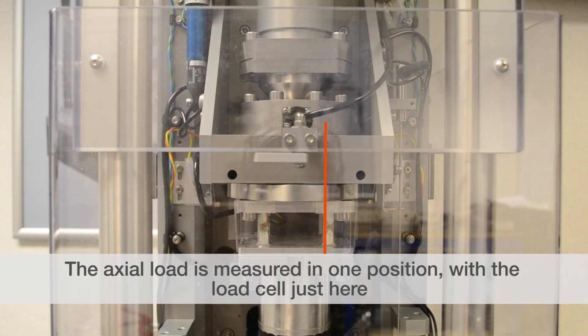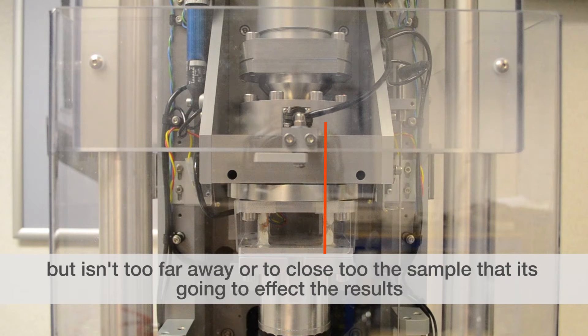The axial load is measured in one position, with this load cell just here. You can see the cable coming out the front of it. Its placement is very important. It needs to be situated in a position that isn't measuring all of the friction from the linear guides, but isn't too far away or too close to the sample that it's going to affect the results.